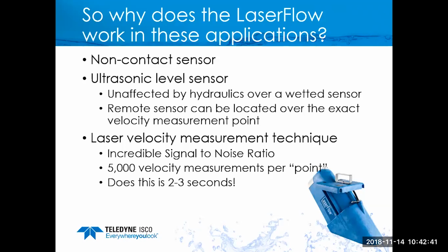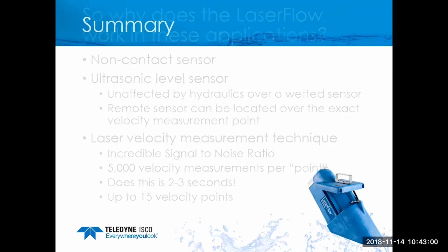So pump station applications, we use them in those all the time. Up to 15 velocity points. So again, 75,000 velocity readings. If it's a billing location, you have AC power, you can run all 15 and get the most representative sampling of your velocity and your flow in that channel.